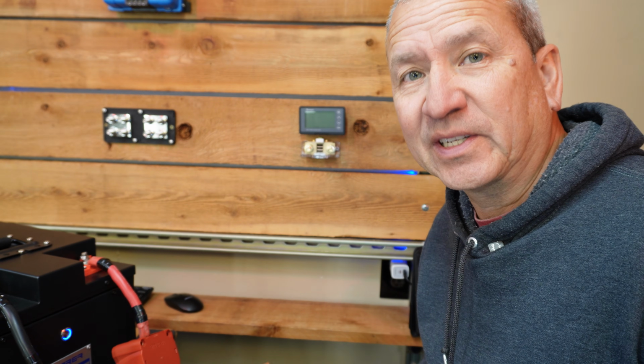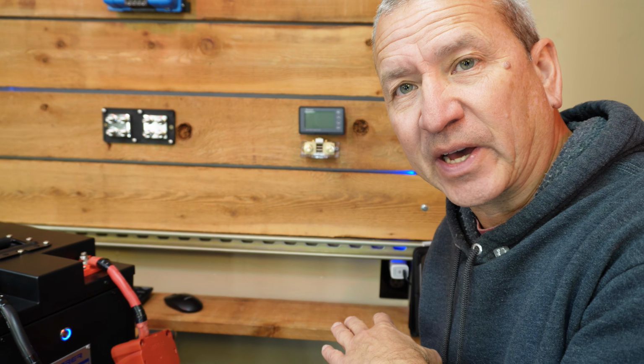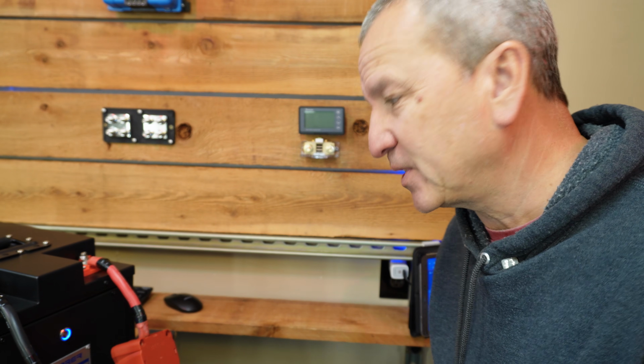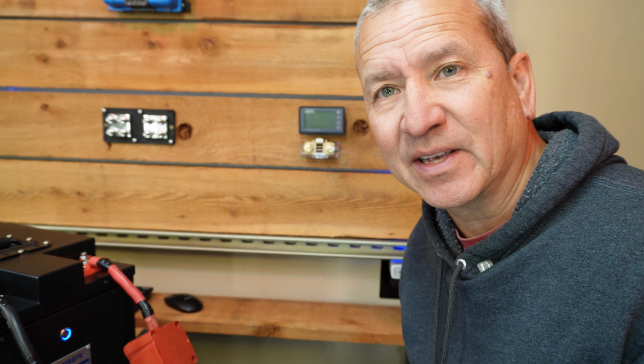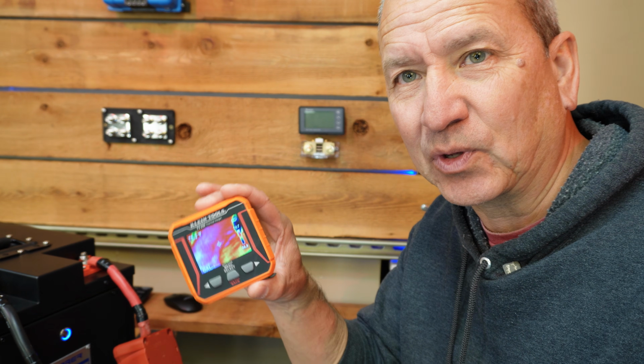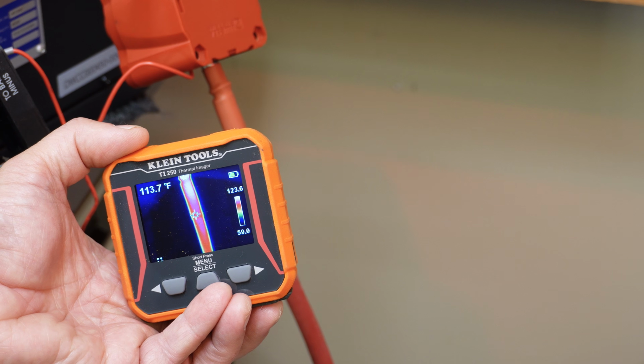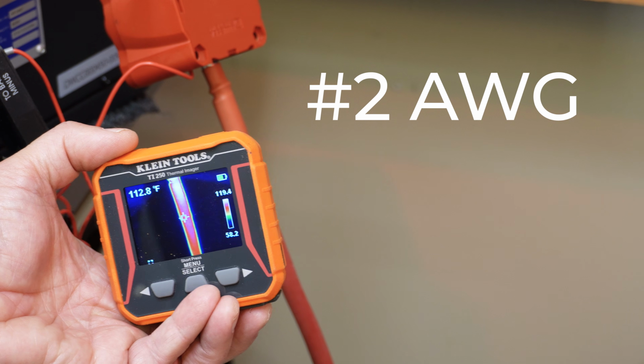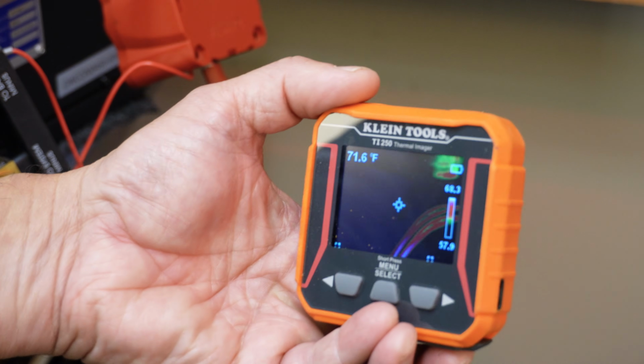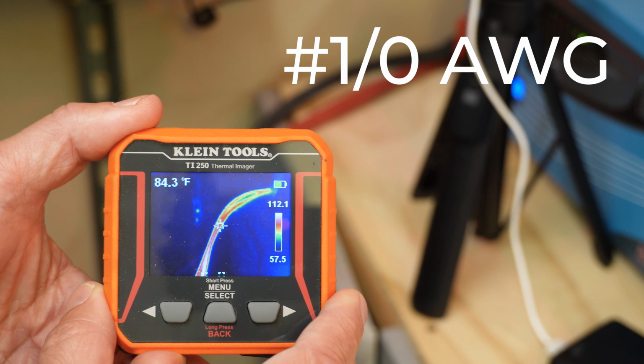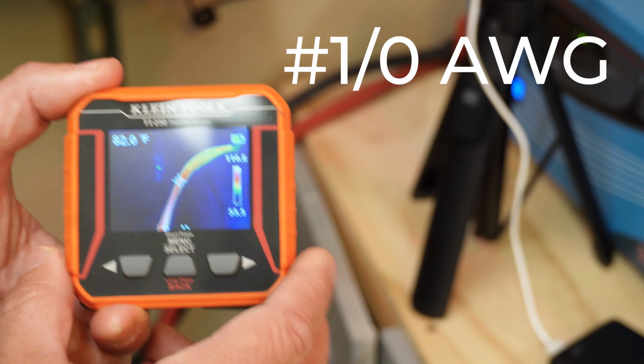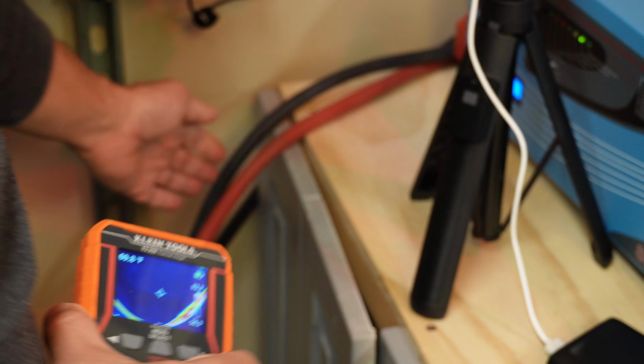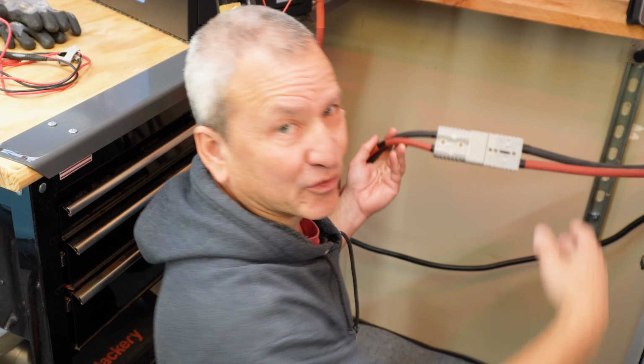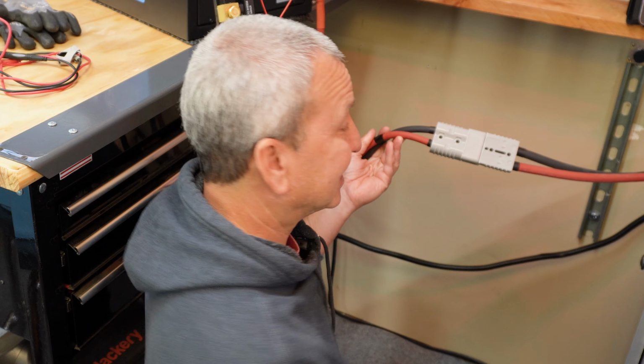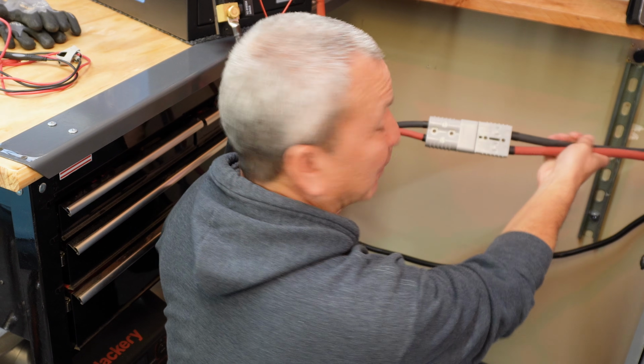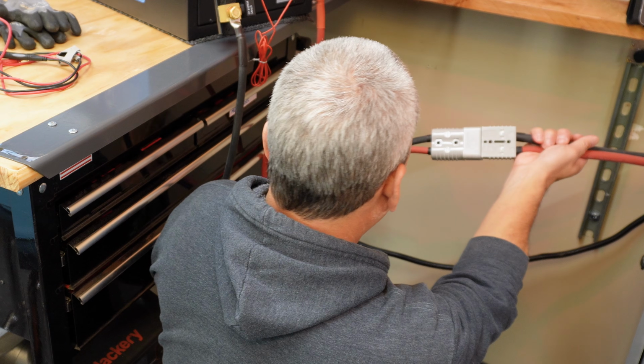Now, while I'm doing this discharge and trying to draw the batteries down, let me show you the difference the cable size makes with my thermal camera. 113, 115 degrees Fahrenheit on this cable. Now let's take a look at the 1/0 cable - about 85 to 89 degrees here. Neither of them are at unsafe levels right now, but cable thickness does make a difference.